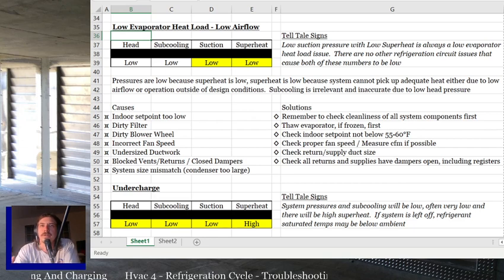Your head pressure is definitely going to be lower than normal, and your suction pressure and your superheat are low, and those are the two most important ones. The bad thing about low evaporator heat load is it makes a vicious cycle, right? Your superheat's low, so you're probably going to start creeping towards freezing, if you actually hit freezing as your superheat and your suction pressure drop.